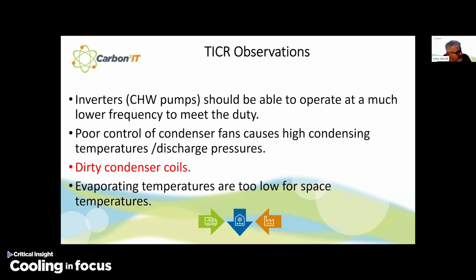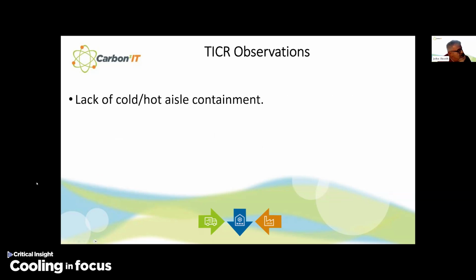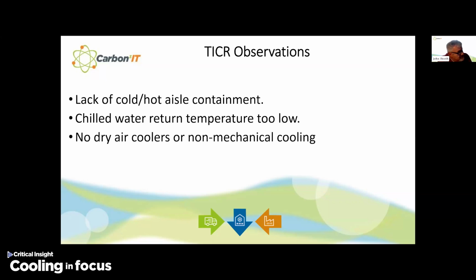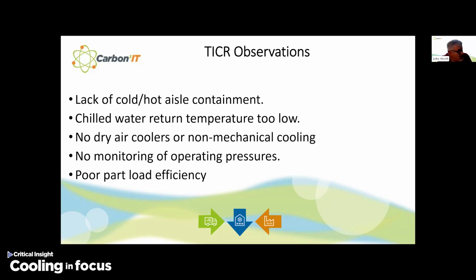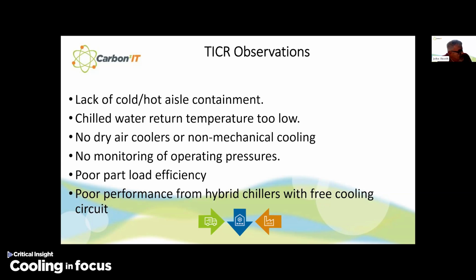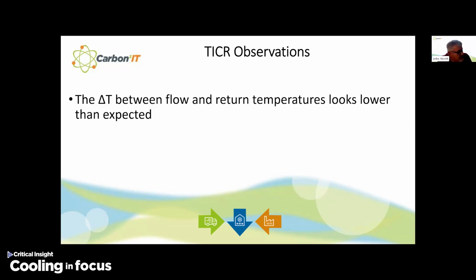And we found that evaporating temperatures are too low for space temperatures. We found a lack of cold and hot aisle containment. We found that the chilled water return temperatures were too low. We didn't find a lot of dry air coolers or non-mechanical cooling. There didn't seem to be any monitoring of operating pressures. We found poor part load efficiency. We found poor performance from hybrid chillers with free cooling circuits. We found the delta T between flow and return temperatures looked lower than expected.